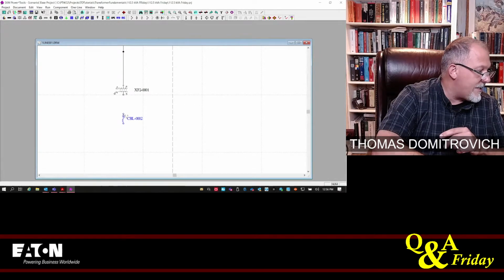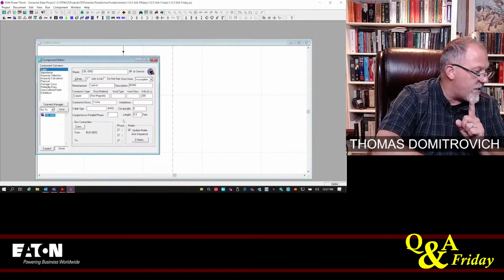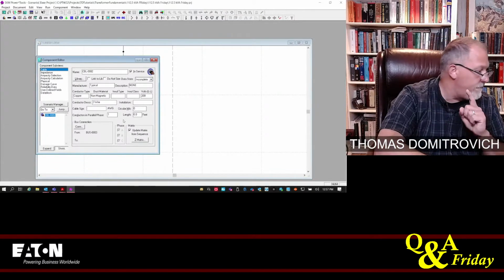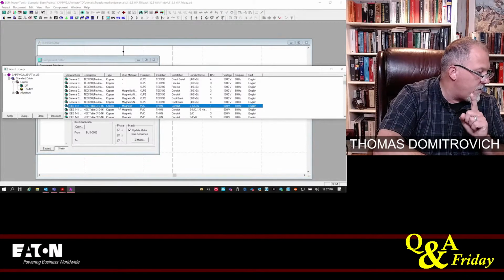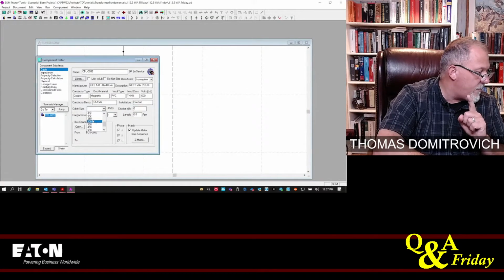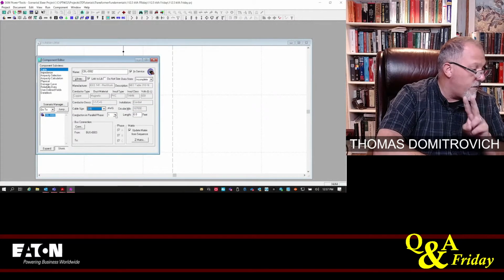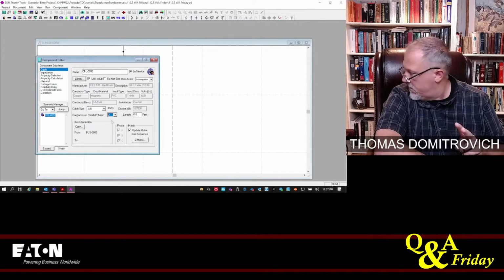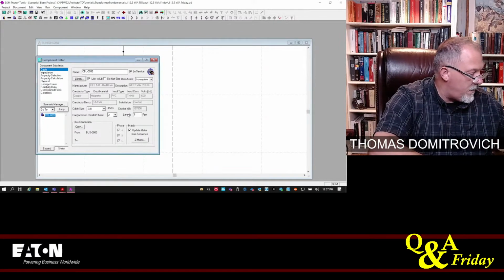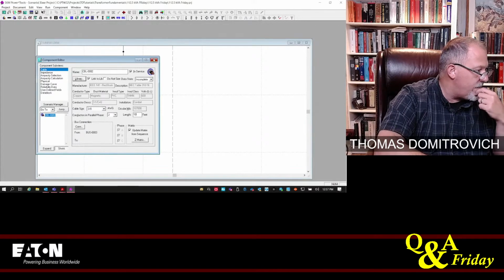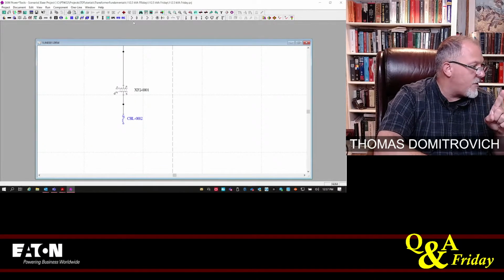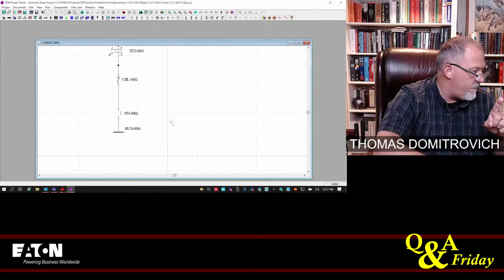All right, so on the secondary, we have a conductor coming off of the transformer, and we said that was going to be a 3-aught. Library, copper, PVC, and we'll make this a 3-aught conductor. 2 of them. No, 1. No, 2. Yeah, quantity 2, and we'll make it 10 feet. All right. So that's the conductor. That will land on a circuit breaker, which will be connected to a bus. And I will have another circuit breaker downstream of that.